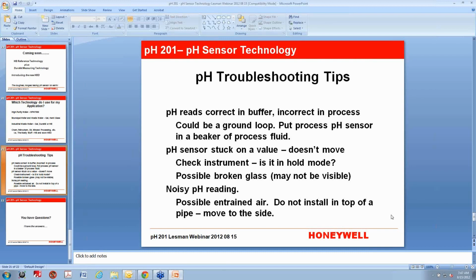And you would see that with any pH sensor. A Durafet would be a little less susceptible to it, but only a little, because we're talking still about a pretty small signal. But the test is to put it in this beaker of process fluid. If it reads correctly, the odds are really, really good that you have a ground loop. The other thing you can do is take a ground strap and take it to earth ground, a good earth ground, and drop it in that beaker and see if the reading jumps. If the reading jumps, that means you definitely have a ground loop. There's voltage in the process, and you're going to have to figure out how to get rid of it.